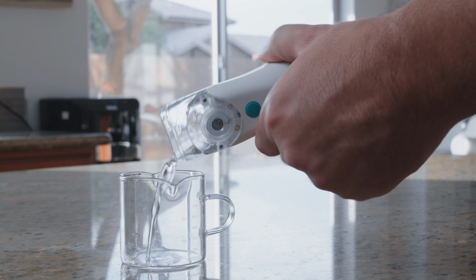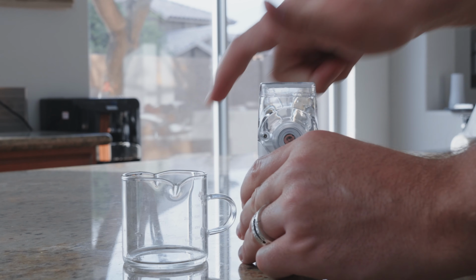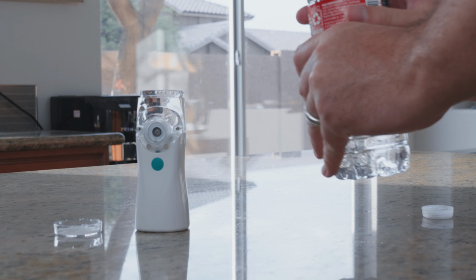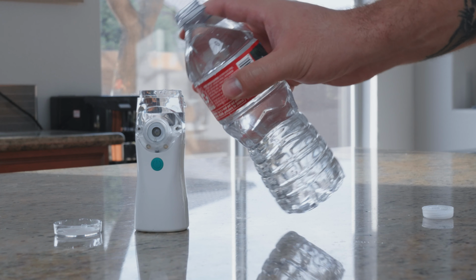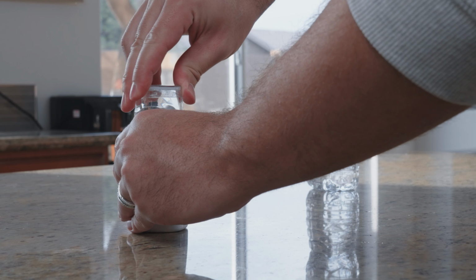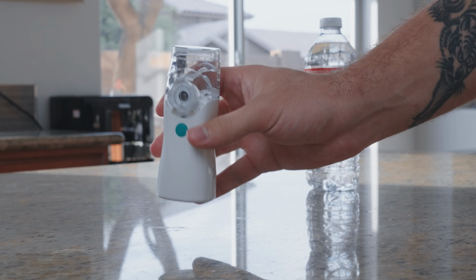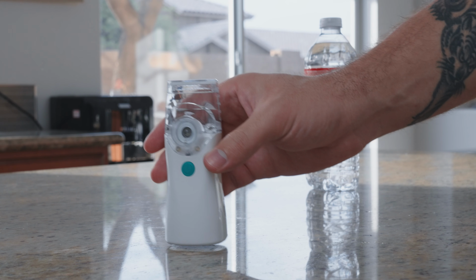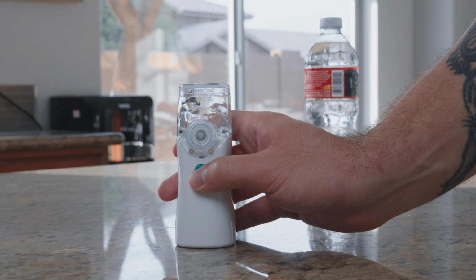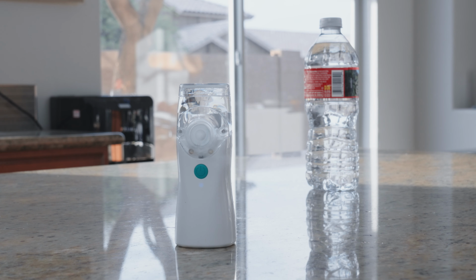After-use care. It is very important to remember to clean your nebulizer after every use. Failure to do so may cause evaporated medicines to solidify on the atomizing mesh plate and clog the mechanism. When the treatment is done, make sure to pour out any possible remaining medicine by removing the lid and gently shaking upside down into a sink. Pour approximately 10 milliliters of purified water into the reservoir and place the lid back on. Gently swirl it around to collect any medicine that may have condensed inside the reservoir. Let the nebulizer run for 2 to 3 minutes and pour out the remaining water.